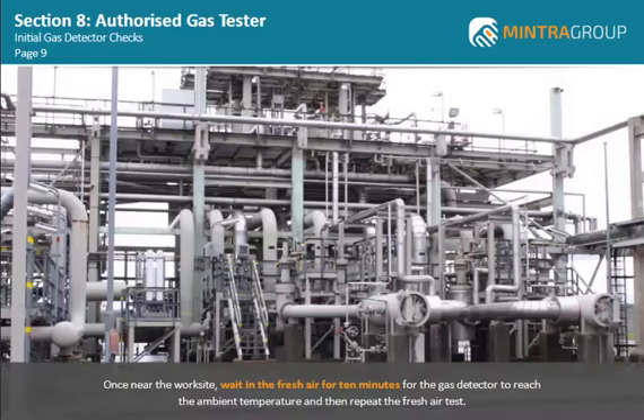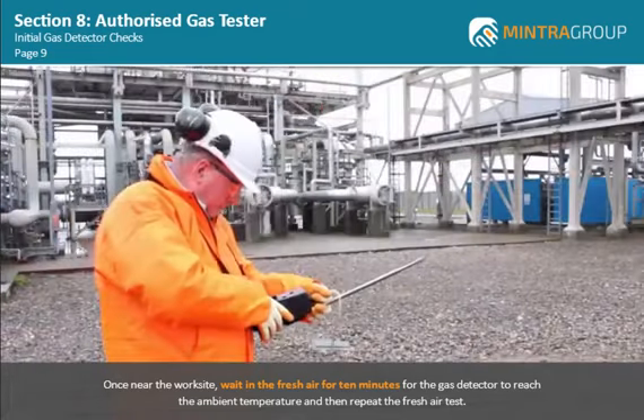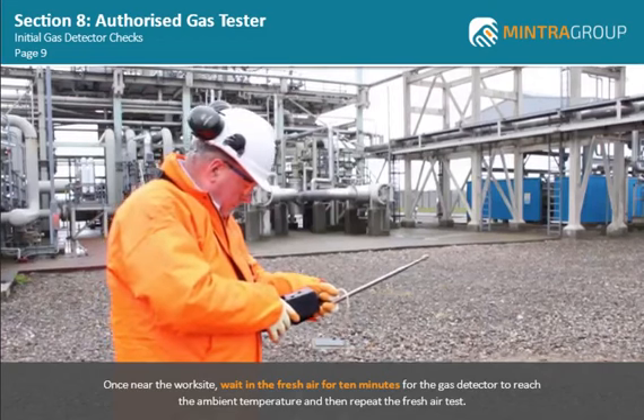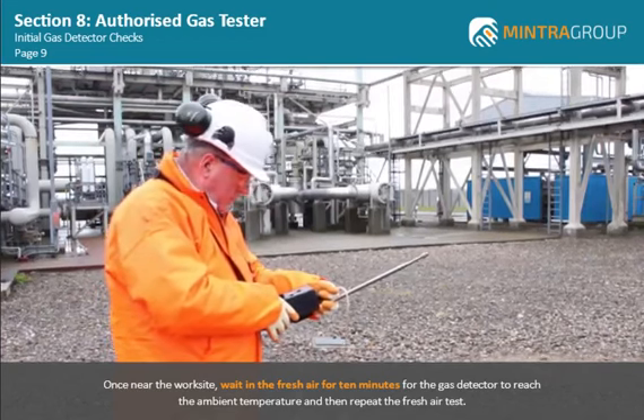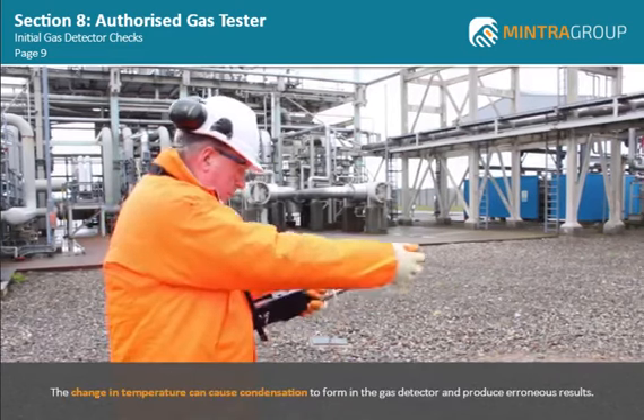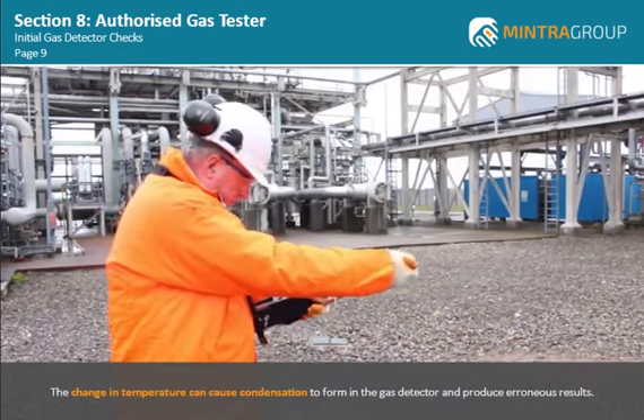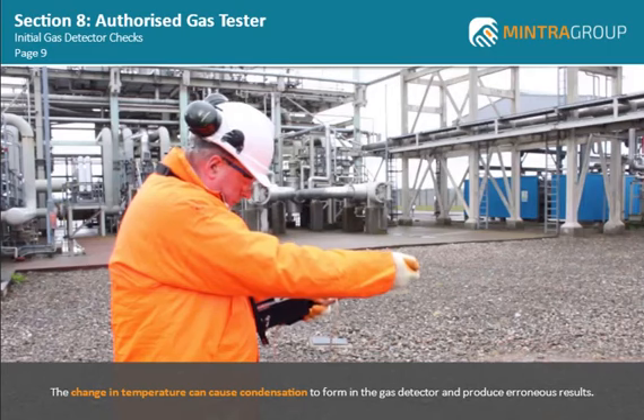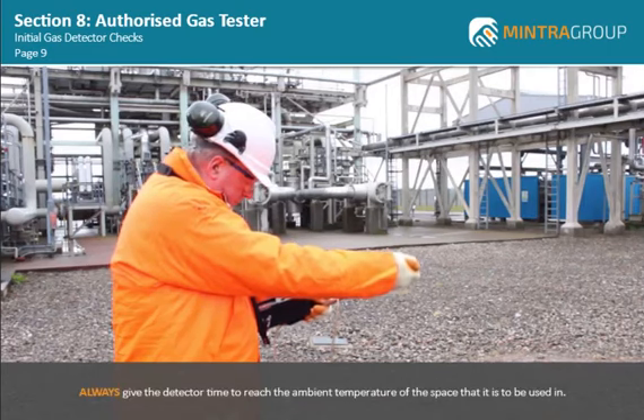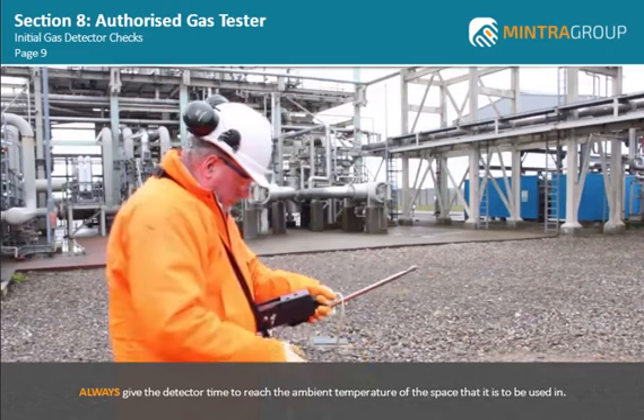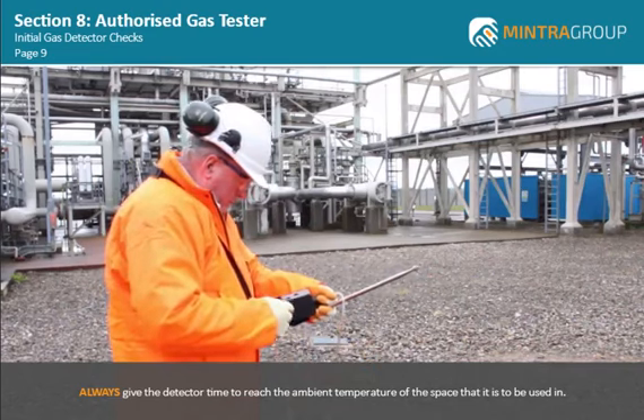Once near the worksite, wait in the fresh air for 10 minutes for the gas detector to reach the ambient temperature, and then repeat the fresh air test. If you are moving the gas detector from an air-conditioned control room or office to a hot or cold environment, be aware that the change in temperature can cause condensation to form in the gas detector and produce erroneous results. Always give the detector time to reach the ambient temperature of the space that it is to be used in.